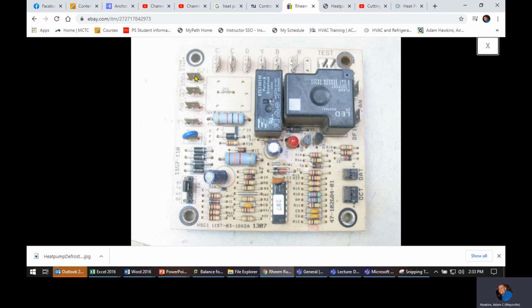And then on your outputs, this one has a Y out. So you're going to have Y in, Y out. Assuming that the board is allowing this compressor to run, Y is going to go out to the contactor, bring the contactor on. And then it has a common coming back, so that's going to let all the commons come back. Well, wait. This is its common. So you got Y out and contactor common, I think is what they're going to call that. And then you've got RV, which is your reversing valve. So B comes in, energizes or de-energizes depending on its position, what it's calling for, and either energizes or de-energizes this RV. RV goes out, goes to the reversing valve coil, and then comes back to common because it has to have a common.